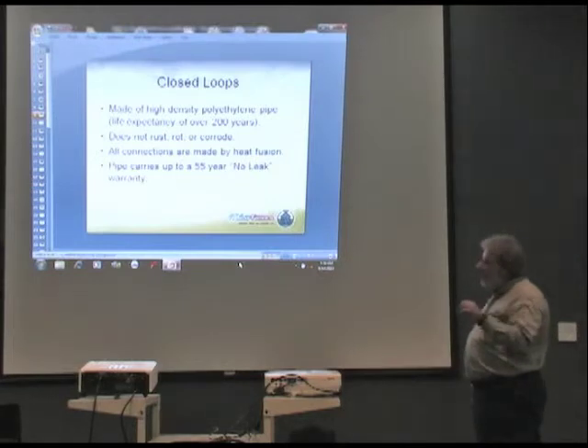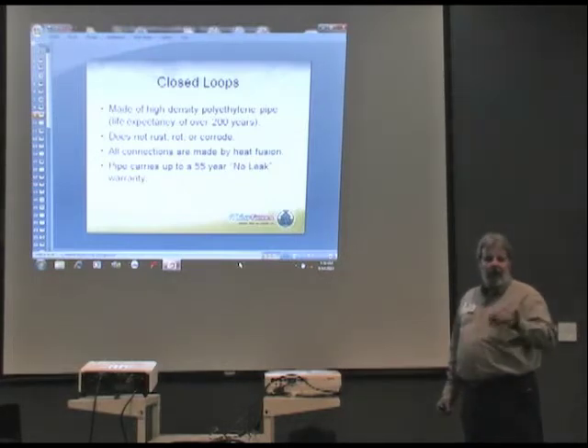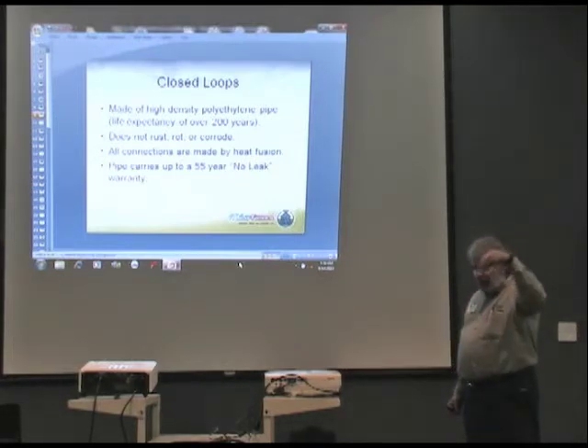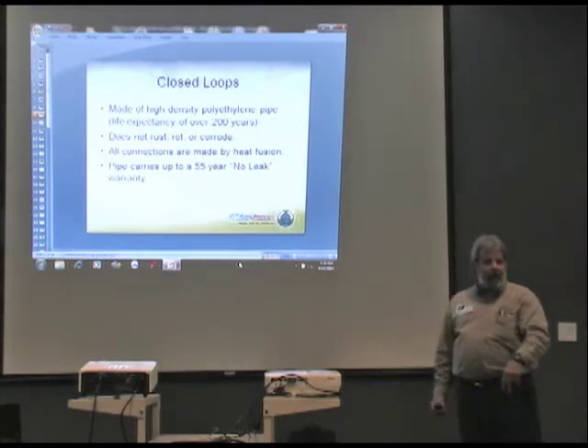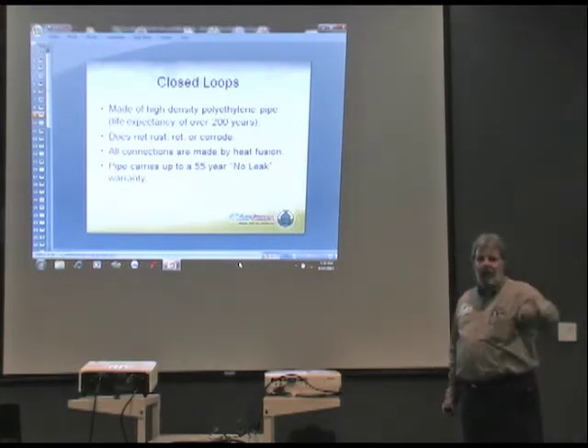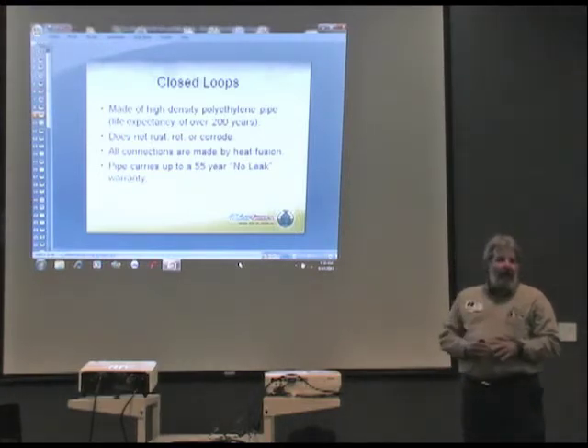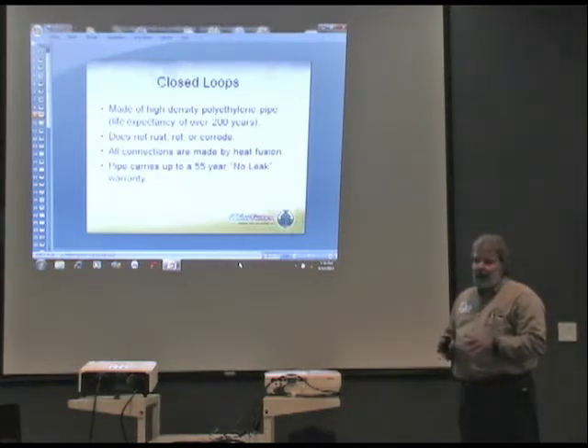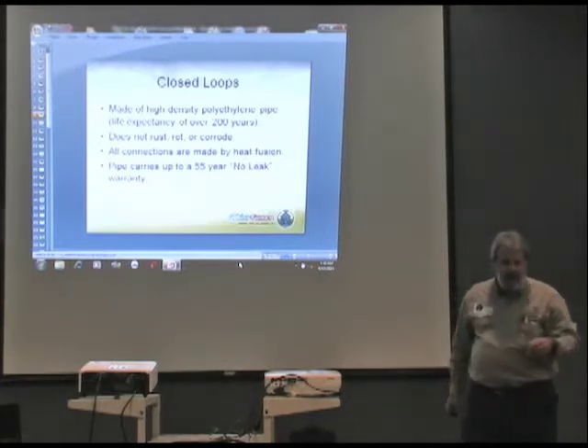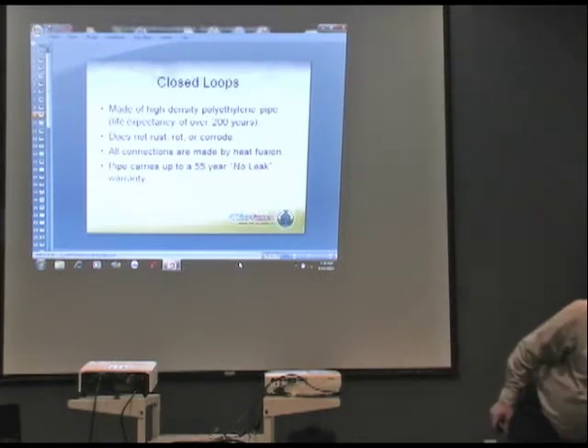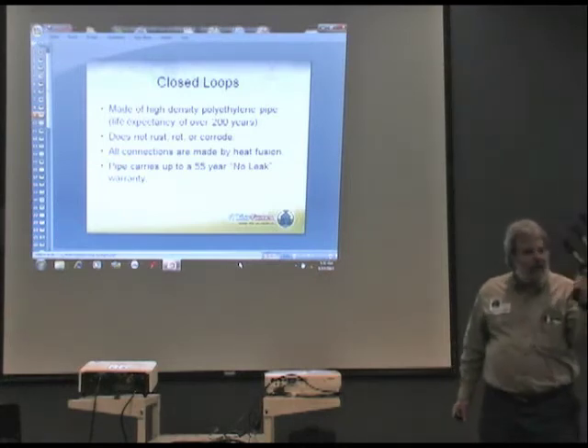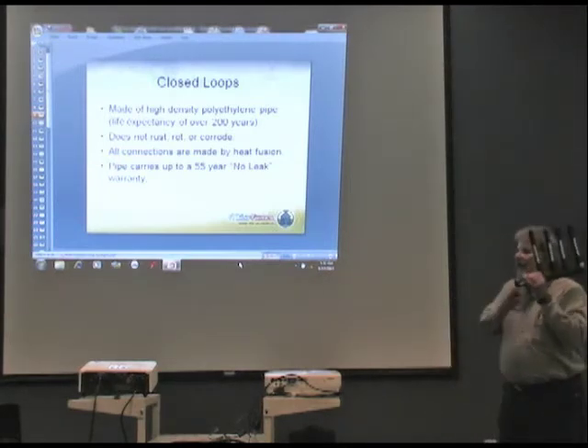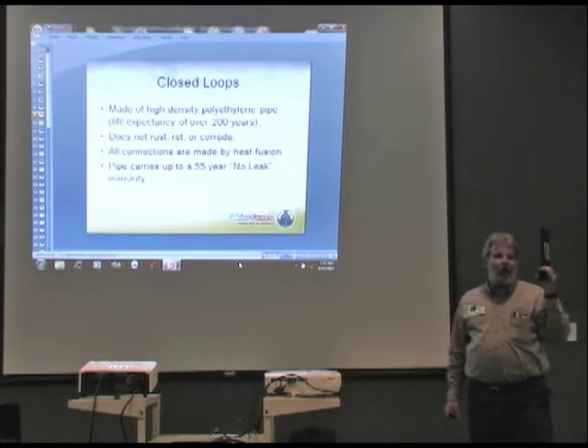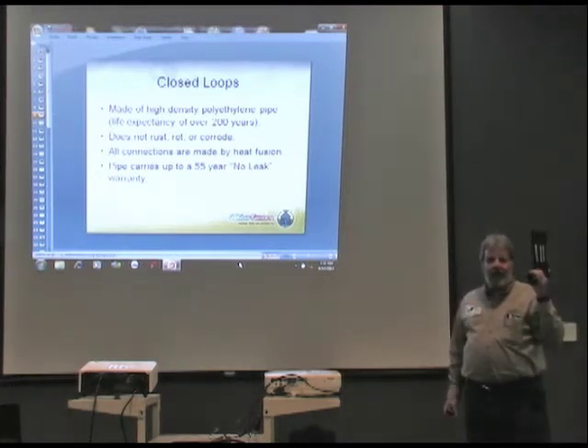What goes out in the loop is continuous. When we go out into a horizontal loop or down into a vertical, there's no joints. It's one continuous loop. The joints are back at what we call the header pit, somewhere outside the house. That's where we take the pipes from the loop and heat fuse them together into something like this, then run 1 1/4 inch supply and 1 1/4 inch return into the house to the geothermal unit.